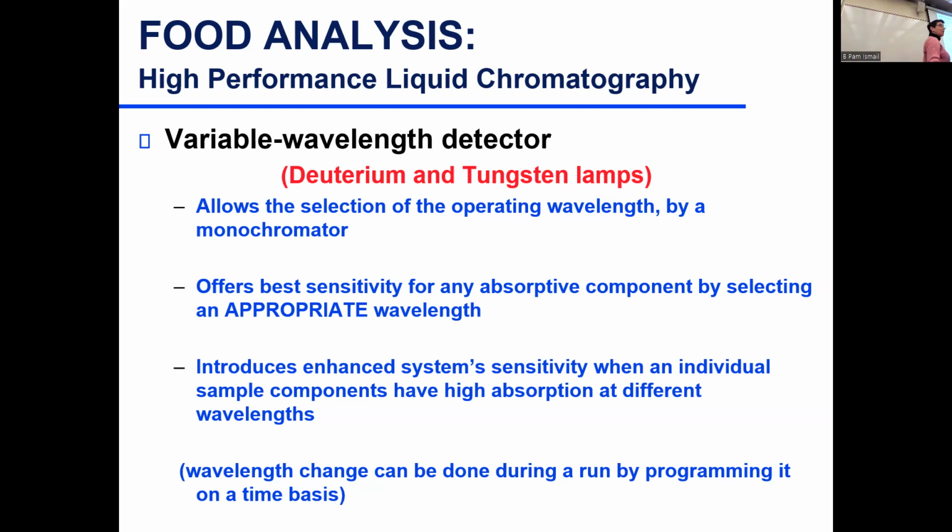Do you remember what lambda max is? I'm going to finish in a minute. What does lambda max stand for? Tam? It's the wavelength at which it absorbs the max. Exactly. So that's where you can select your appropriate wavelength. You can sometimes select 2, or even at a certain time point in the run have the UV detect at a different wavelength. You have the option of 2 wavelengths in these detectors.